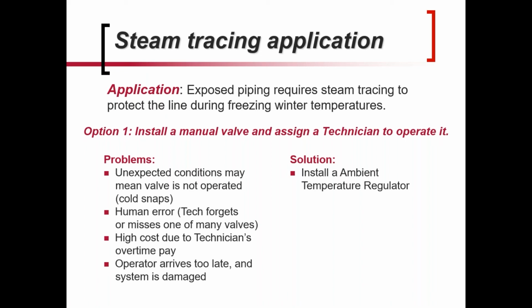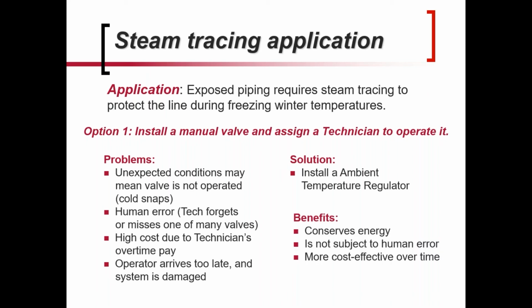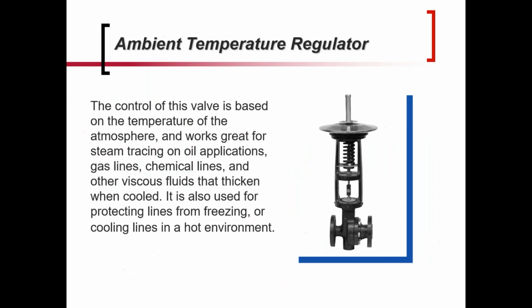And so one of the challenges that everyone faces is trying to keep up with all of the small tasks. And these aren't weekly things that you're doing. So it's easier to forget these, easier to overlook these, but you can look at installing an ambient temperature regulator, and that measures exactly as it states, ambient temperature in the air around it. So it conserves energy, don't have to worry about the human error. On the water application we're talking about, you set it for 38 degrees, and if it goes below that, it opens and lets steam into the steam tracing lines.